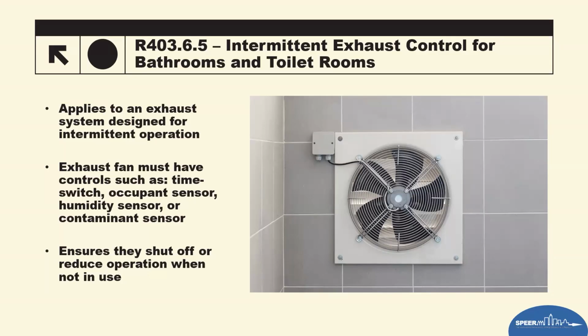It's also important that if the fan is serving as whole house mechanical ventilation, it's not part of this requirement. But if they're standalone and they're not part of mechanical ventilation, which most of the time in most of Texas they're not, then it's going to have to follow this as well. So from a design and compliance standpoint, this means verifying whether the exhaust truly is intermittent. If yes, then it must follow controls. Coordinate with the equipment selection, ensuring wiring and commissioning supports automatic shutoff, and then document the control type for inspection.